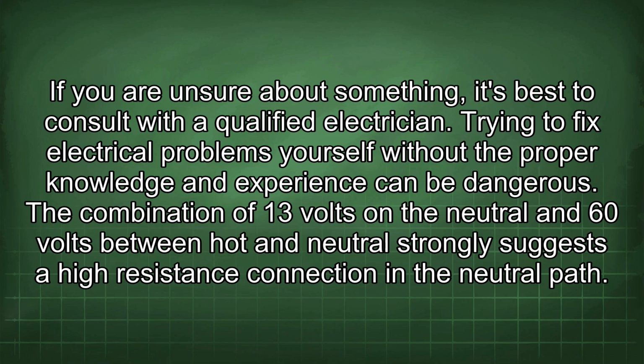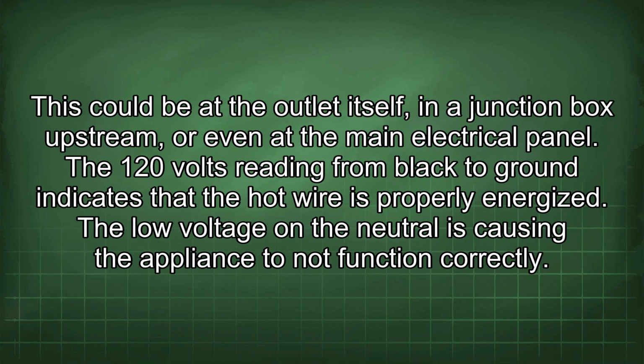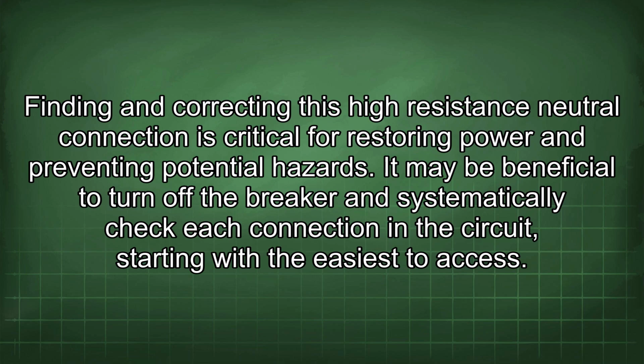The combination of 13 volts in the neutral and 60 volts between hot and neutral strongly suggests a high resistance connection in the neutral path. This could be at the outlet itself, in a junction box upstream, or even at the main electrical panel. The 120 volts reading from black to ground indicates that the hot wire is properly energized. The low voltage on the neutral is causing the appliance to not function correctly. Finding and correcting this high resistance neutral connection is critical for restoring power and preventing potential hazards.